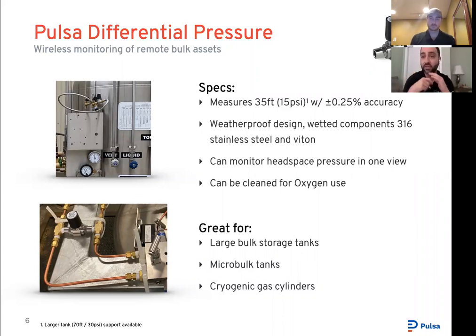You can set it up at your site as you see fit, at your leisure. That 15 to 20 minutes can include software, hardware, and network access — the first one might take a little longer as you get familiar with the software. Network connectivity is basically minutes. The sensors are weatherproof and outside the box support 35 feet of tank height (420 inches), and we can get sensors up to 70 feet tall by request. Our customers report that installation takes about 70–80% less time than competing solutions.